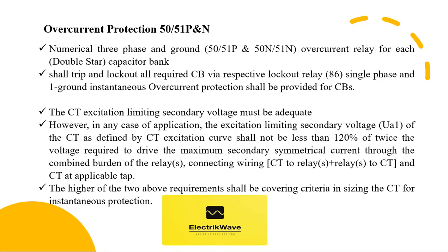However, in any case of application, the excitation limiting secondary voltage of the current transformer as defined by the current transformer excitation curve shall not be less than 120% of twice the voltage required to drive the maximum secondary symmetrical current through the combined burden of the relay. The higher of the two above requirements shall be the sizing criteria for the current transformer for instantaneous protection.